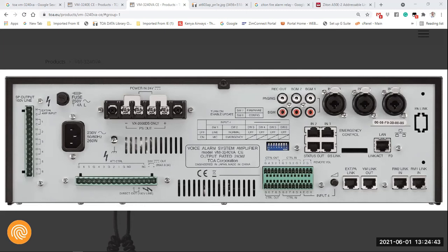Right. If you can see what I'm typing on the chat column. So what I'm saying is, if you take the same cable that we had here, which is the orange-white as control input number 1, the green is control input number 2, the blue pair control input number 3, the brown pair control input number 4. If you take the same cable and you push it into here, only the orange one will work as control input number 5, and the brown pair will work as control input number 6. This is why I was saying you only have 6 emergency controls and 8 general.